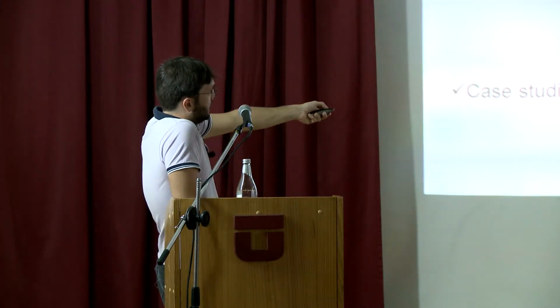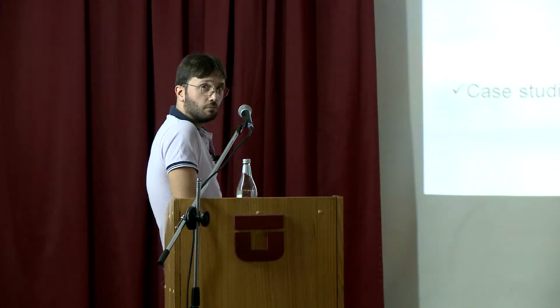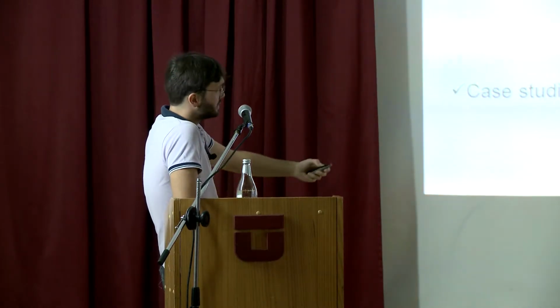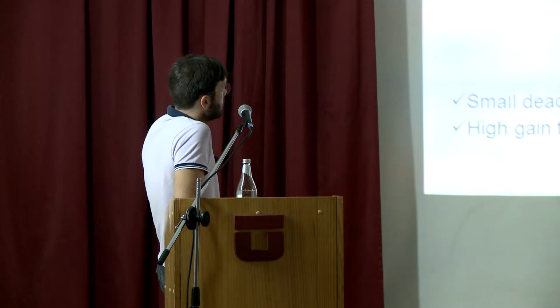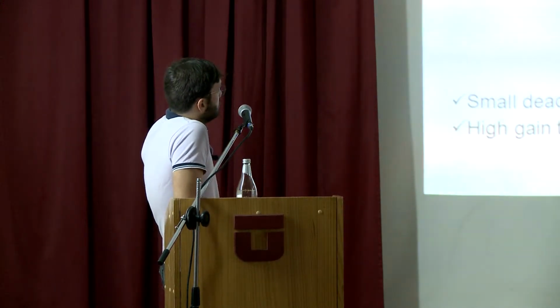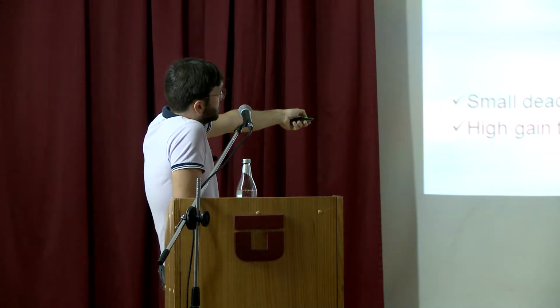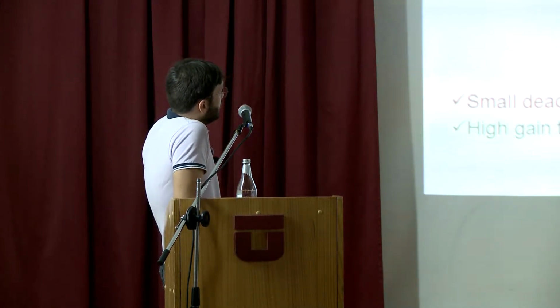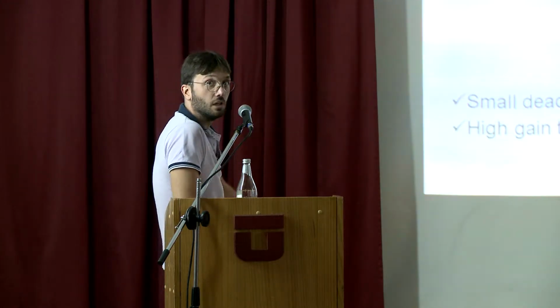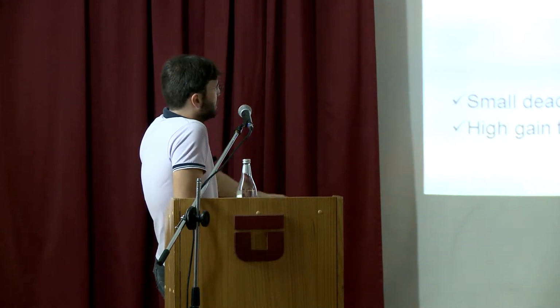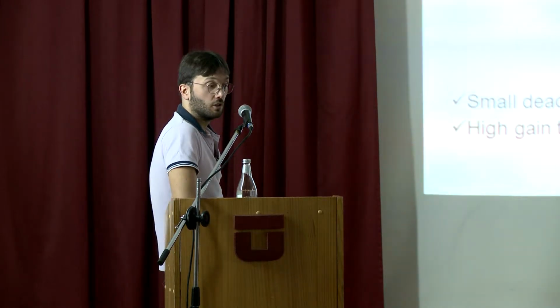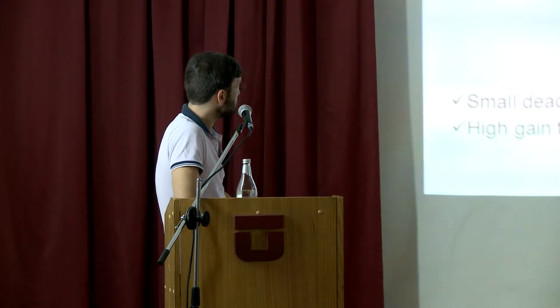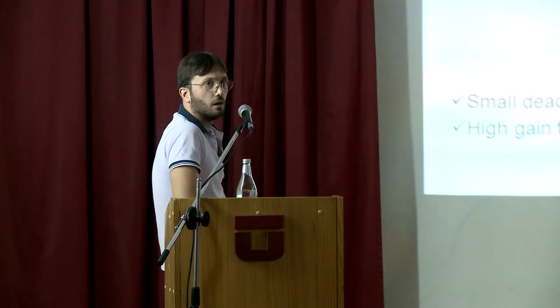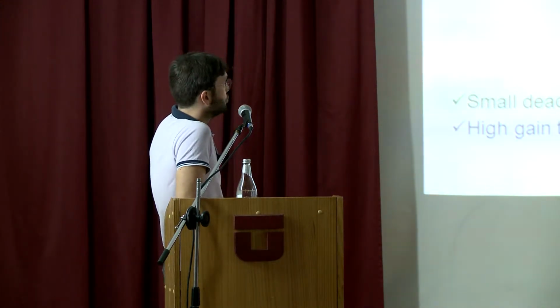So the idea is that one of these will be substituted by a smart transformer, and the smart transformer will do something very simple: power control. If the voltage goes down, I will inject capacitive reactive current to try to lift the voltage up. If the voltage goes up, I will inject inductive reactive power to take it down. So very, very simple.